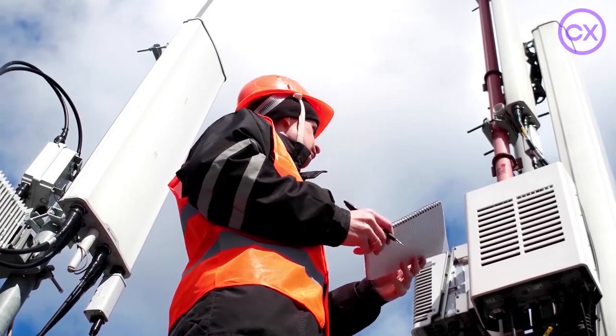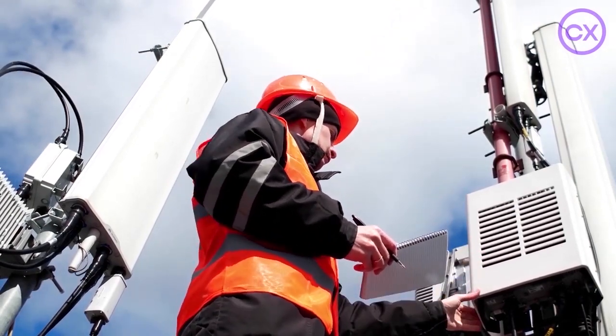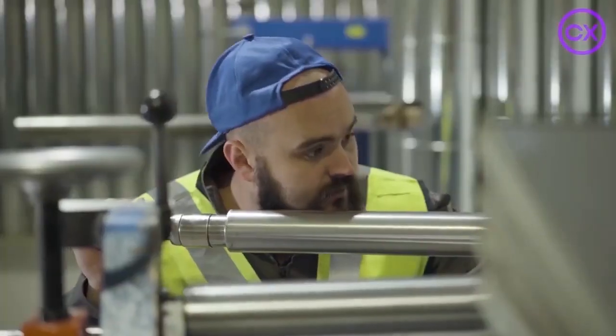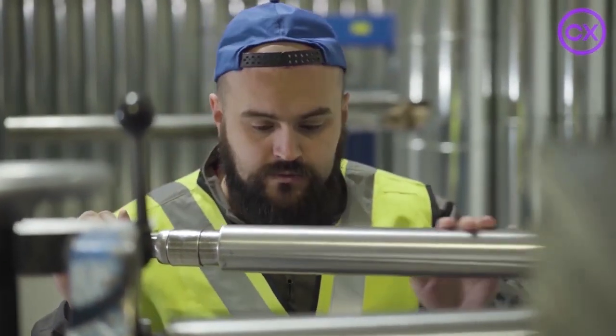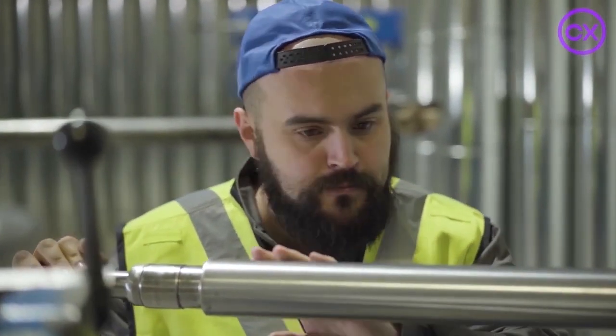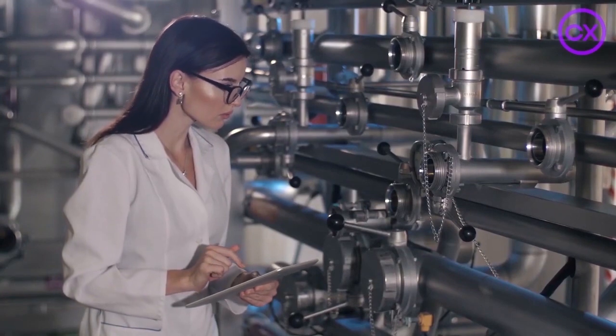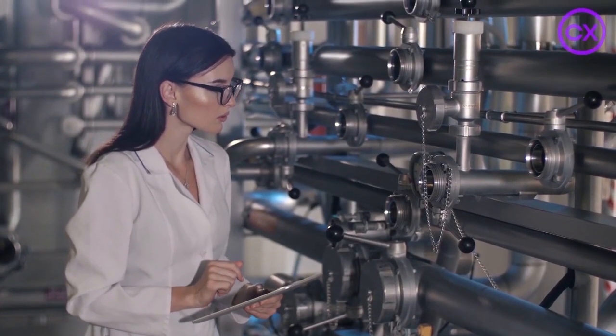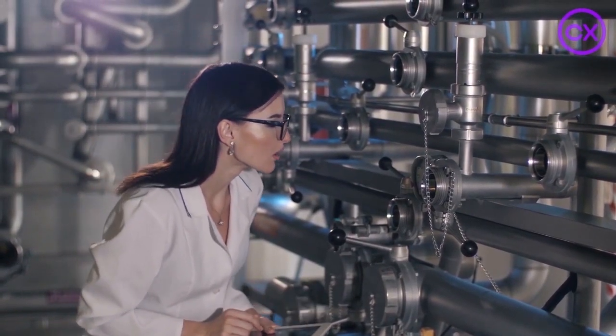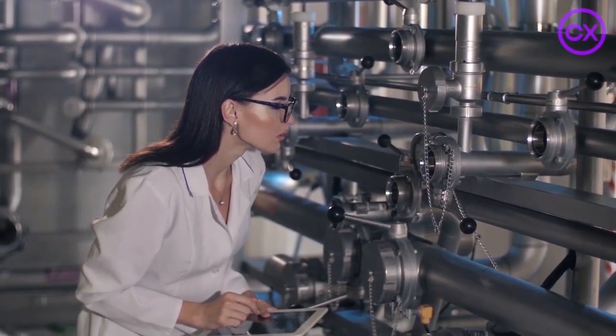So to summarize, the main difference between QC inspections and commissioning inspections is that QC inspections confirm that the equipment is installed correctly, such as piping has been flushed, motor and pump have been torqued correctly, all components are aligned, and commissioning inspections confirm that the equipment functions correctly, such as it's rotating in the correct direction and it's drawing the correct current with the proper pressure and flow rates.